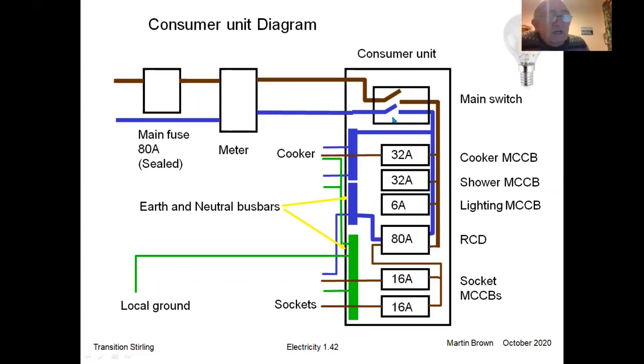There's the big main switch, which breaks the circuit coming in from the supply. There's the meter, the electricity meter, which will measure all the power that you're using. And last but not least, here's the main fuse. Now, you've got all this protection here, so why do you need a main fuse? Well, you've got to protect in case there's a short circuit in the meter or perhaps in this switch or something. Because if you had a short circuit here, it would damage all the wiring coming into your house. So there's another fuse here.